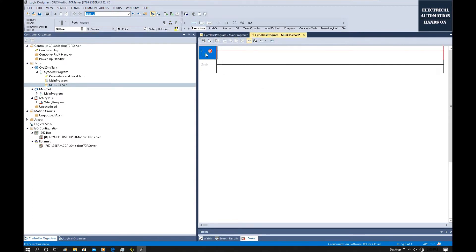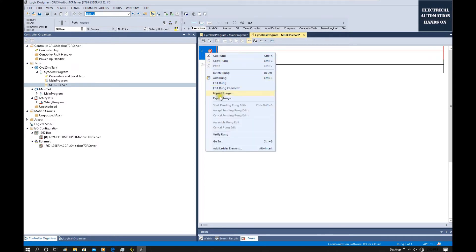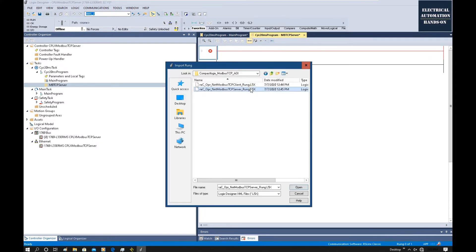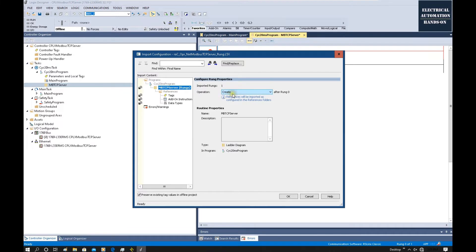Following the manual, at this rung we right-click and click Import Rung. Select the Modbus TCP Server — that is the slave function. Click Open. This creates and imports the AOI into this rung. After import, from the Add-On Instructions it imports tags here, and from the data type it also imports strings and user-defined UDTs.